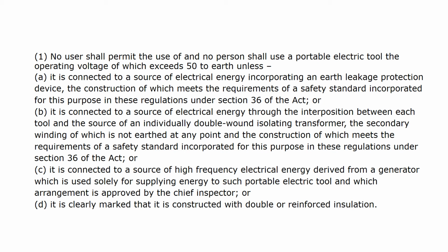It is connected to a source of electrical energy through the interposition between each tool and the source of an individually double wound isolating transformer, the secondary winding of which is not earthed at any point, and the construction of which meets the requirements of a safety standard incorporated for this purpose in these regulations under Section 36 of the Act, or C. It is connected to a source of high frequency electrical energy derived from a generator which is used solely for supplying energy to such portable electrical tool and which arrangement is approved by the chief inspector, or it is clearly marked that it is constructed with double or reinforced insulation.